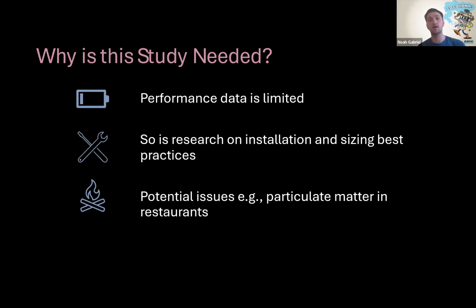Same thing is happening here. Lab tests are usually about 80 degrees ambient with a pretty low input water temperature. In the real world, with varying conditions, things like recirculation, performance is often going to be a little bit worse, but still good. So we wanted to test that. Is the performance a lot lower, or just a little lower than rated specs? Wanted to figure that out.